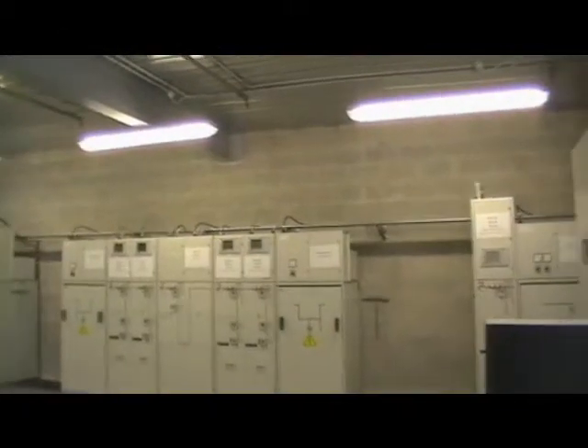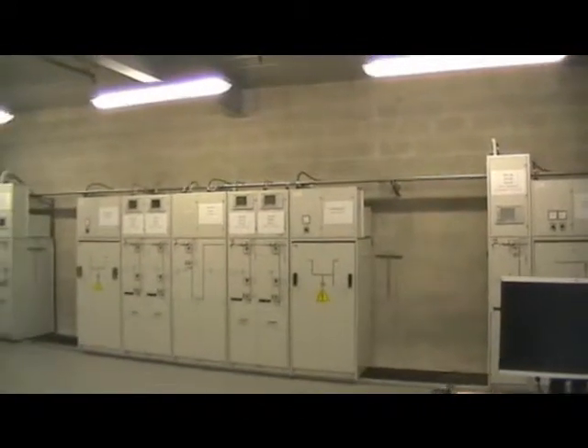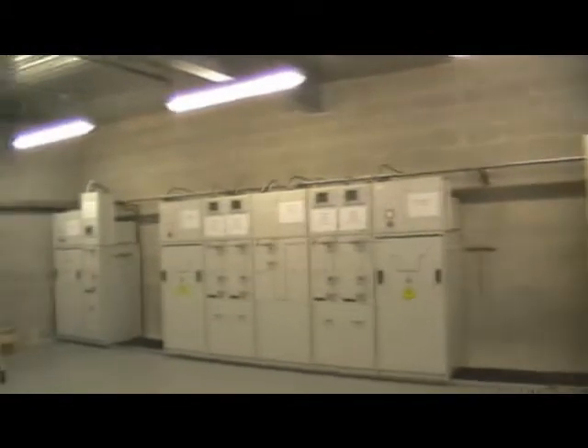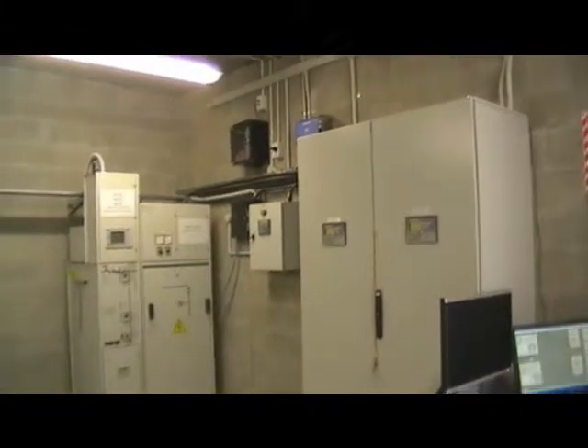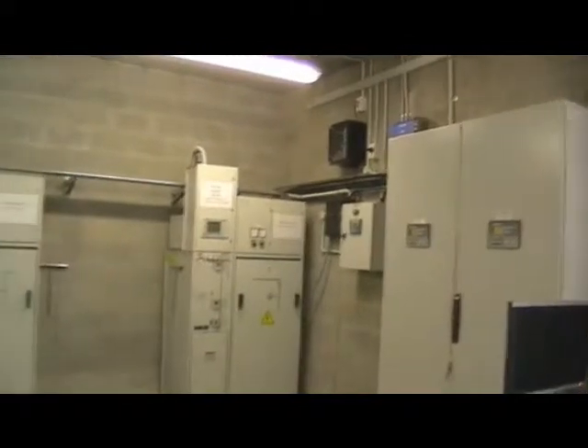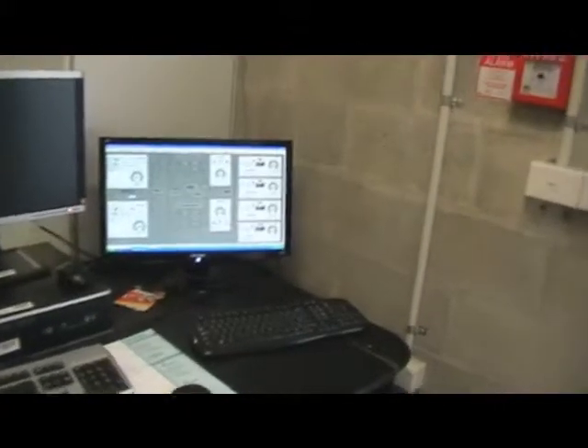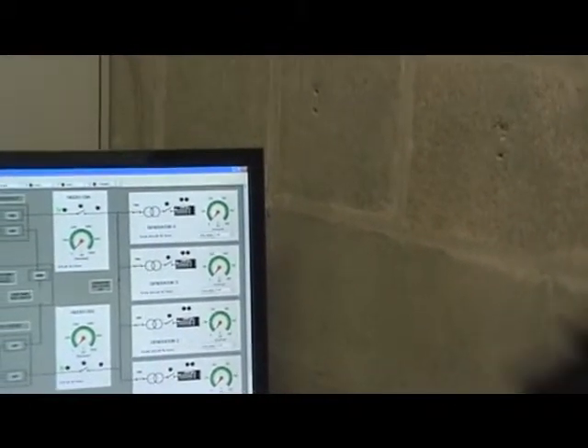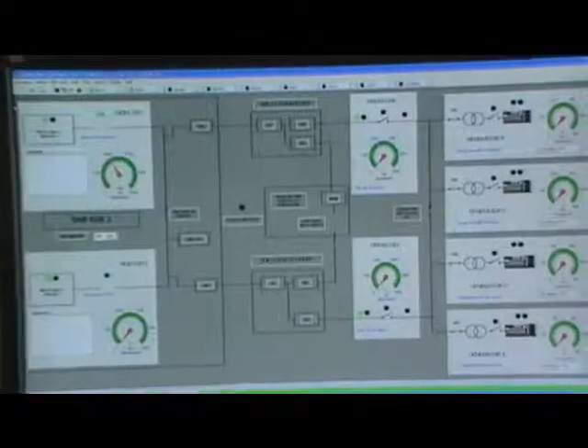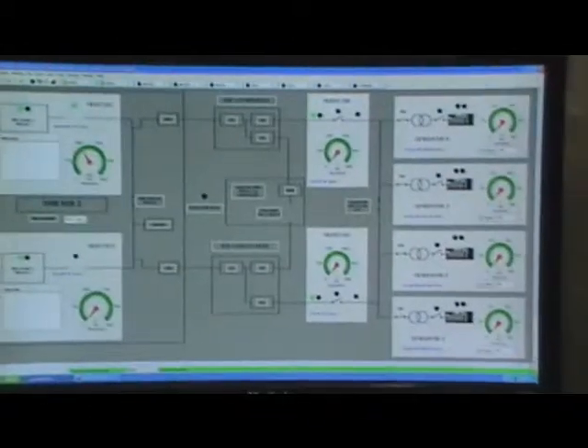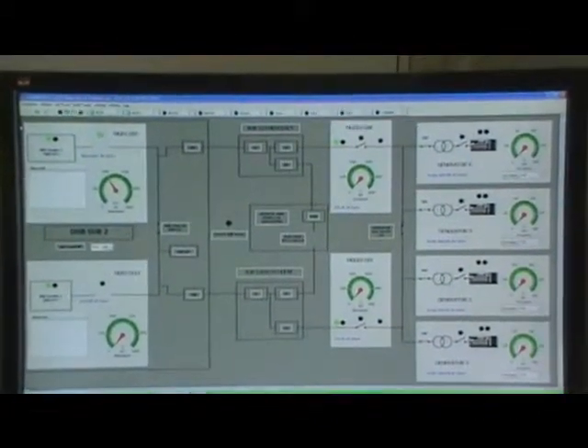This is our 11 kV switchgear. The 2 extreme left and right go out to our 11 kV ring, which comes around the side, and the middle ones are fed from the transformers, which transform up from the 400 we generate at to 11 kV. This is basically a SCADA system there, and there's our 4 plants on the right. Those are our 2 injection points. This is the schematic for our ring, and those are our 2 incomers from Well. It hasn't quite been handed over to us yet, so we're still in the commissioning stage of it.